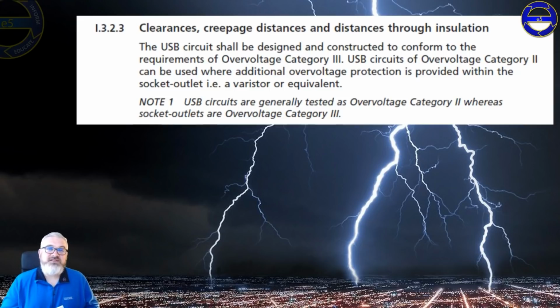The note is the fascinating thing. USB circuits are generally tested to category 2, whereas sockets are overvoltage category 3. So what they're saying is in the latest BS 1363-2 standard, the USB component shall be tested to category 3, as will the actual body of the socket. So that's a step up in the standard, which is a great thing. Probably doesn't answer all the questions that you're wanting to write down there.